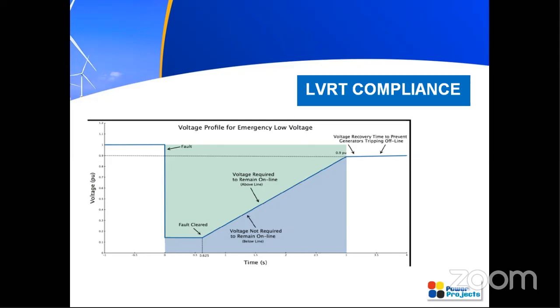Okay. And one more thing is that the real power should retain its value of 90% of the pre-fault level within 1 second of the restoration of voltage. That is, if your voltage is restored within 1 second, your real power has to be restored to 90% of the pre-fault level, which was the voltage level during the pre-fault condition. So of that, 90% should be restored within 1 second. That is what the grid code recommends. That is also to be noted. So all these come under the LVRT study. This is a very, very important study that has to be carried out when we go for integration of wind farms with the grid.